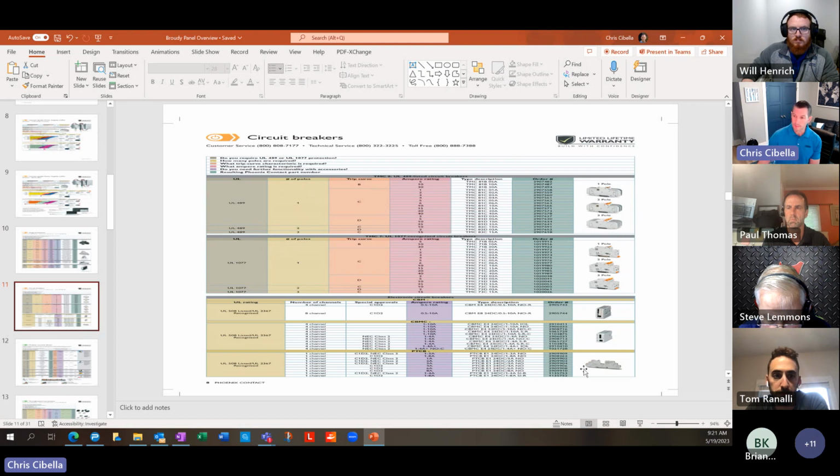So what's going on here is this bottom circuit breaker is very thin. It's about 6.2 millimeters wide. It is a single channel circuit breaker, and you can buy it in fixed values, meaning 2 amps, 4 amps, 5 amps, etc. Or you can buy them in versions that are adjustable. So they have a push button on the front and also an LED, and you can set these things, 1 amp, 2 amp, all the way up to 8 amps.